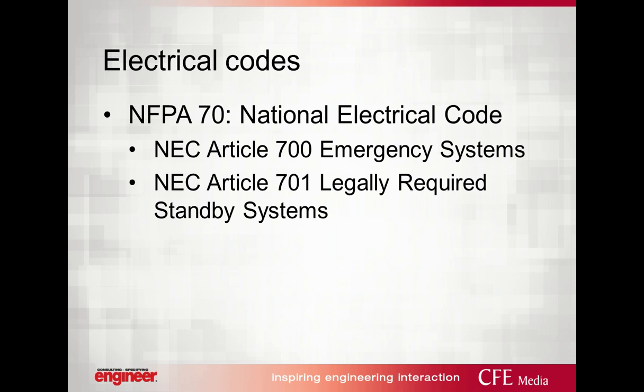My task is to discuss mostly in regards to the NFPA 70, or the National Electrical Code. The National Electrical Code identifies two of the criteria for emergency systems and legally required systems, Articles 700 and 701. Specifically, Article 700 will attempt to cover egress lighting, exit signage, fire pumps, fire detection and alarm systems, emergency egress elevators, safety communication within a building, and industrial processes where severe injury could occur.